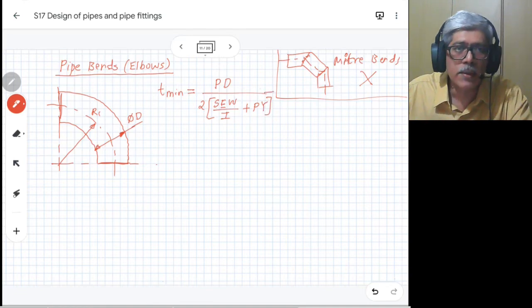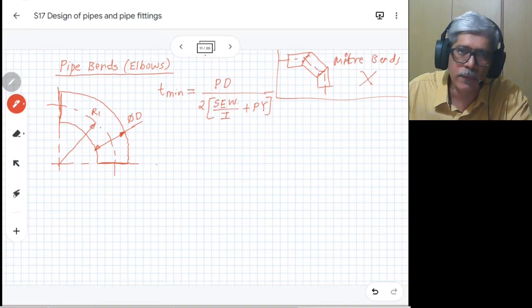Where all the terms: P is the pressure, D is the outside diameter, S is allowable stress, E is the joint factor, W is the factor which depends on the temperature, and Y is taken from the table.